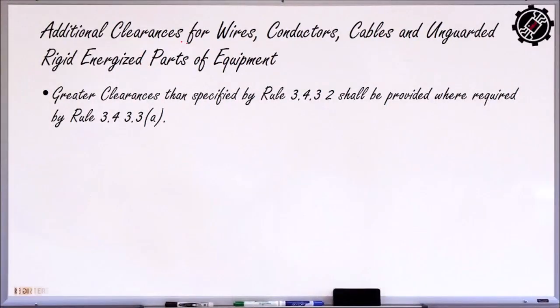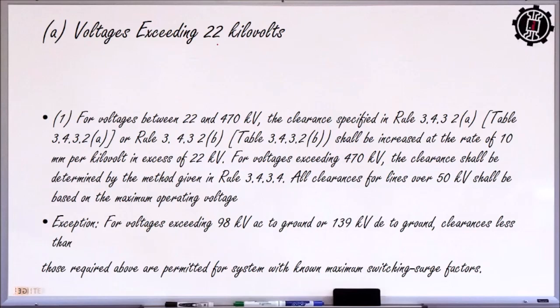So additional clearances for wires, conductors, cables, and unguarded rigid parts of equipment. So greater clearances than specified by 3.4.3.2 shall be provided where required by this rule. No? So if it is recommended to go beyond what is given on this table, no? Yung mga table for clearances. So voltage exceeding 22 kilovolts. Yung kanina lahat na yun that is below 22 kilovolts.